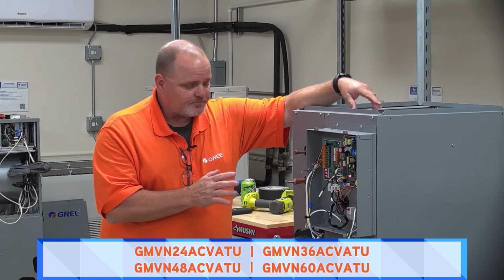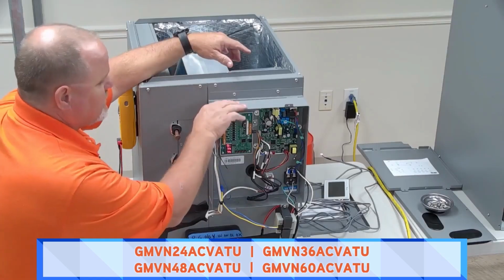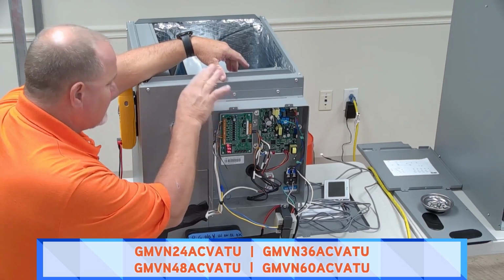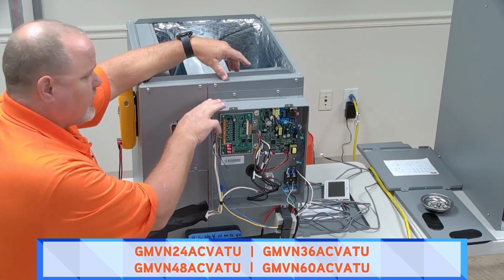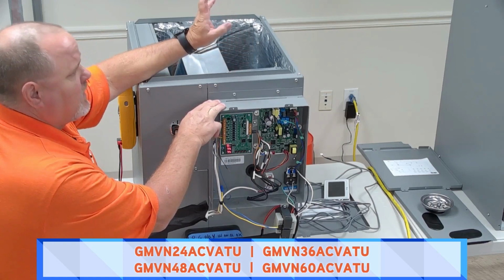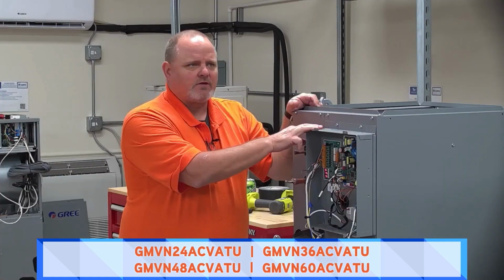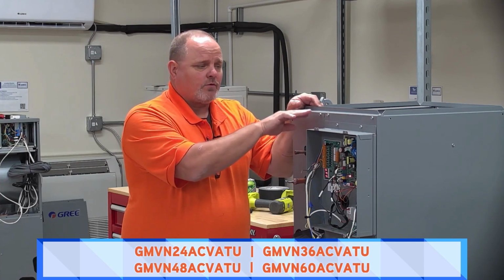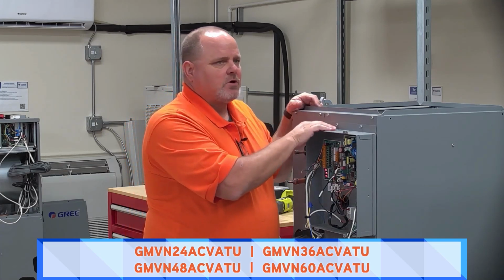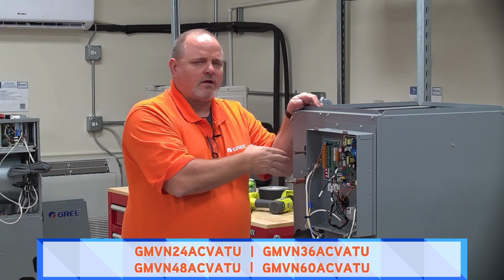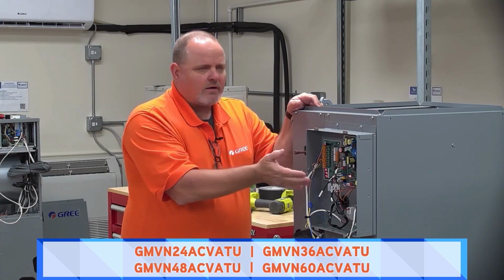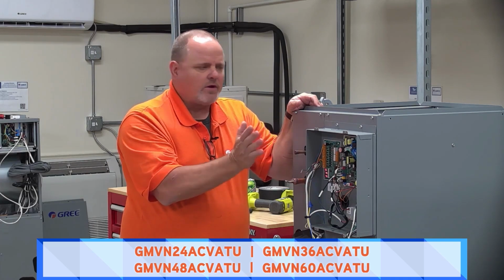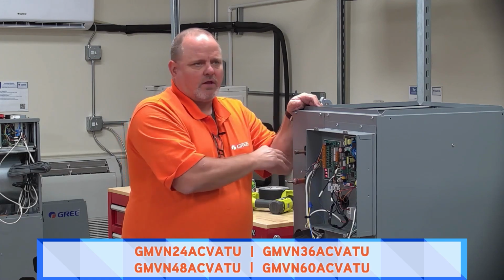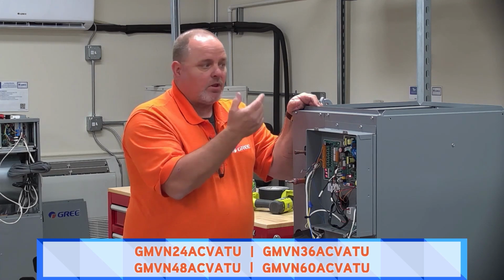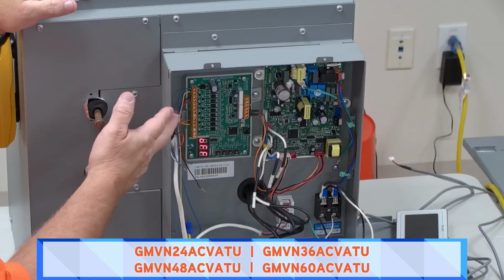The way they come out of the box, I've added some other things to this, but you're going to have this control box that's already mounted to the front of the coil. Again, these are prototypes. Once we got the prototypes, we realized that might be an issue with venting on some of the gas furnaces, so we had them change it up. On the production coils, this can easily be moved to the right-hand or left-hand side. You will have pre-punched holes there. The wiring is all plug and play and color-coded, so there's no way you're going to goof that up. If you want it on the left or right side, it's not hard to move at all. You pop the plug out of the side, put it in the front, and move the control box to the other side.